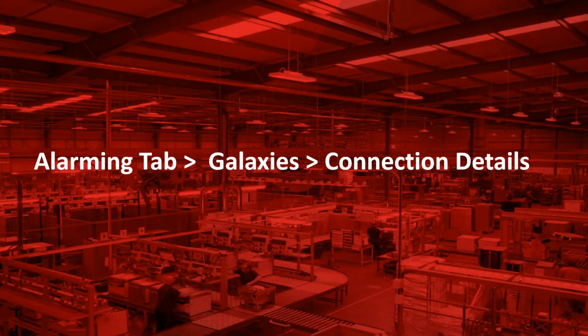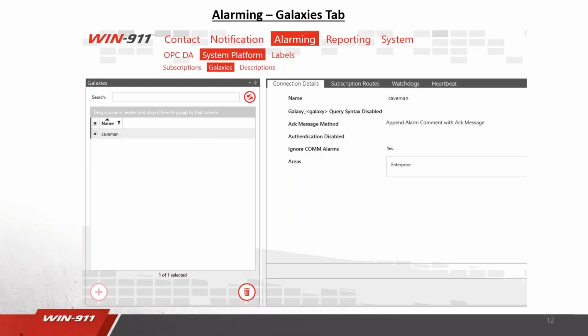So now we're going to talk about creating the connection. Here's where you have the option to put in your Galaxy name, and if that box was checked back on your System Platform for the Galaxy syntax, you would check that box there. Then to bring in the alarms, we need to have areas set up. A lot of times people will put the parent area in this section and then use the subscriptions to bring in certain objects under that area. Or you can bring in other child areas as well through subscription routes. But the parent area would have to be set into this connection details first.